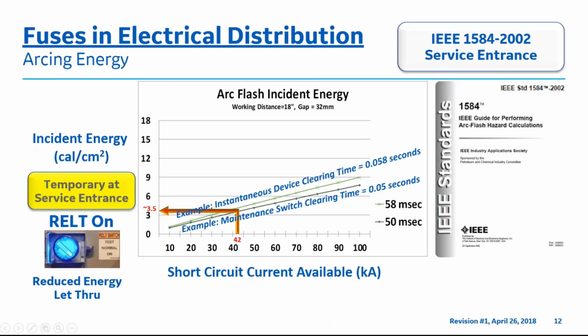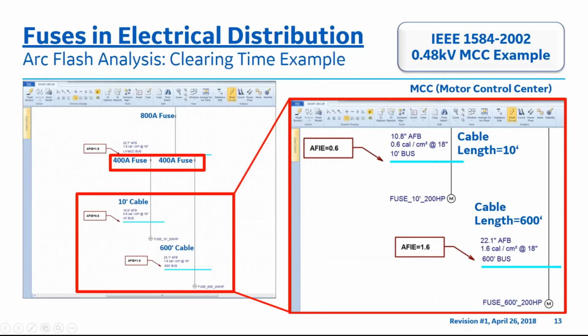The next slide will be an apples to apples engineering analysis of why the arcing current clearing time is important for fuses. Here is a screenshot of a low voltage motor control center example based upon the IEEE 1584-2002 arc flash equations. This example of this apples to apples analysis for fuses consists of a system with two upstream 400 amp fuses. These fuses protect two equally sized 200 horsepower motors downstream.